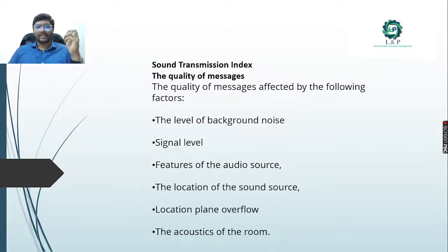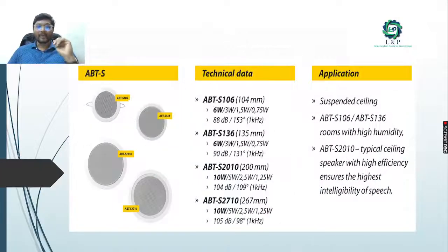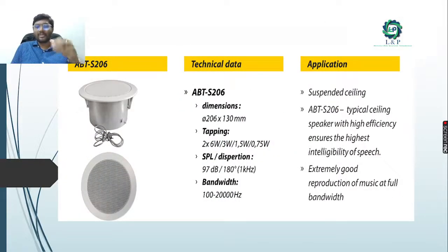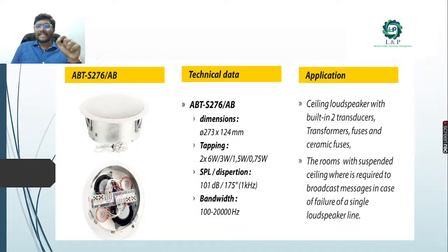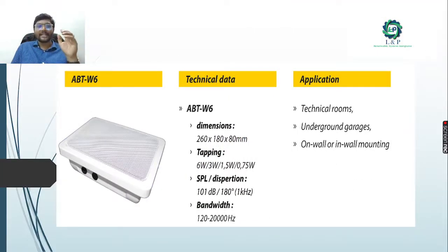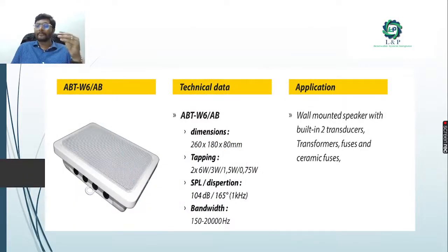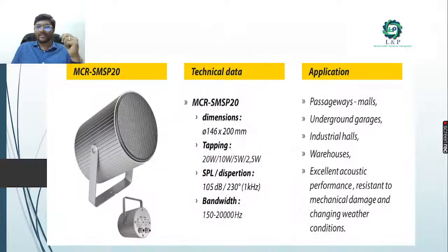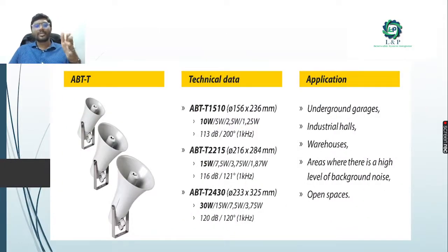The sound transmission index quality is affected by: level of background noise, signal level, features of the audio source, location of the sound source, and the acoustics of the room. Suspended ceiling speakers are commonly used for PAVA systems. There are ceiling loudspeakers with inbuilt dual transducers, transformers, fuses, and ceramic elements - used in technical rooms, underground garages, and recessed mountings. Volume speakers with similar components are used in passageways, malls, underground garages, industrial halls, and warehouses.